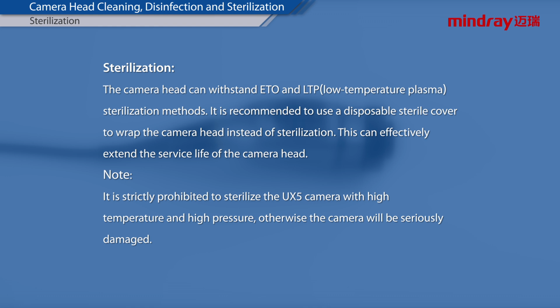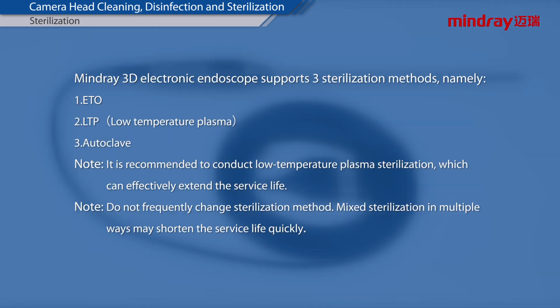Note: it is strictly prohibited to sterilize the UX5 camera with high temperature and high pressure. Otherwise, the camera will be seriously damaged. Mindray 3D electronic endoscope supports 3 sterilization methods, namely 1. ETO, 2. LTP, low temperature plasma, 3. Autoclave. Note: it is recommended to conduct low temperature plasma sterilization, which can effectively extend the service life. Note: do not frequently change sterilization method. Mixed sterilization in multiple ways may shorten the service life quickly.